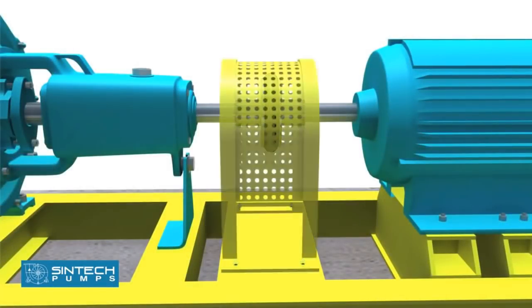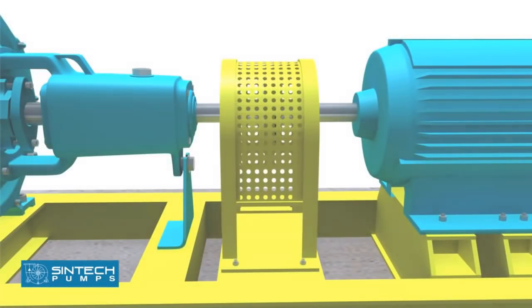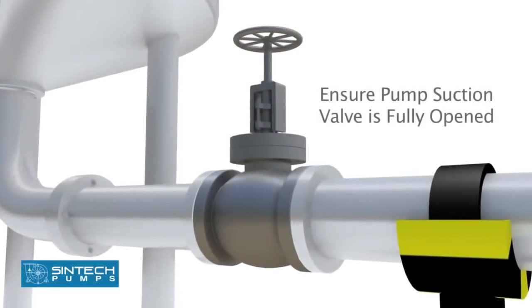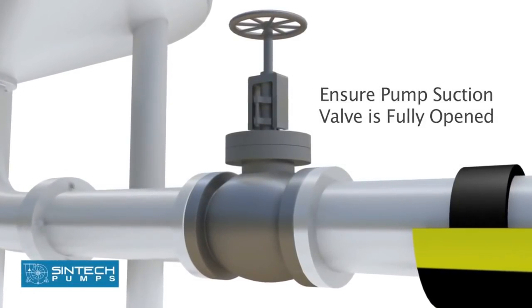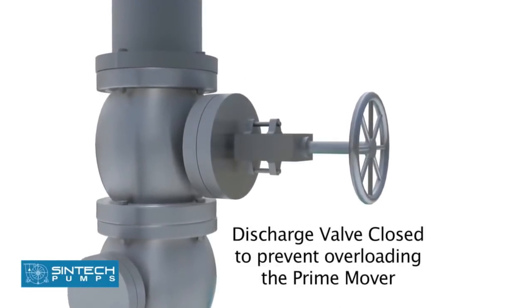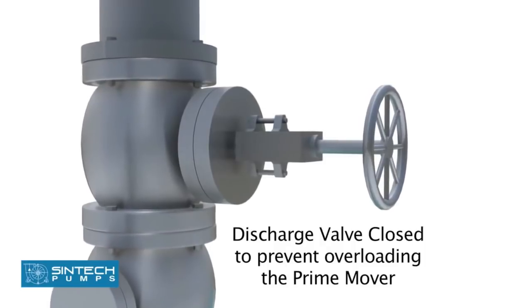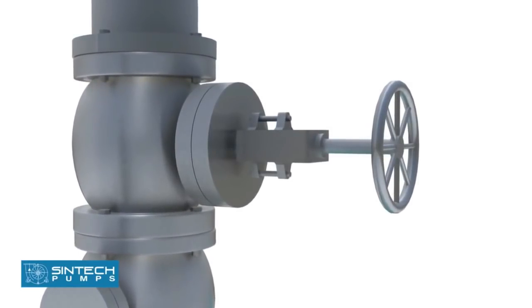Place the coupling guard and tighten the bolts. Ensure that pump suction valve is fully opened and all joints are checked for any leakage. The opening of the discharge valve is kept closed as this prevents overloading the prime mover.